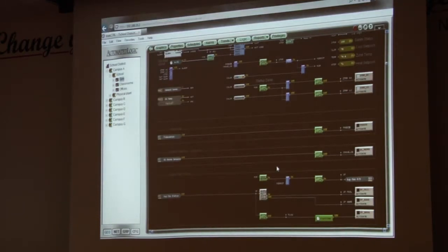The next thing you're looking for is a temperature. A temperature is something that varies. It's not binary. So you're looking for a dark gray hot dog on the left-hand side of your screen that has AI on it for analog input, and it's going to show a little red picture of a thermometer. And that's all that'll really be in there in your systems. I mean, if you start dealing with metering and stuff, we have another hot dog. It shows some purple lines. It's a pulse, but we're not going to deal with pulse. Even if we put a pneumatic module into your system, the pneumatic value is still analog, right? It varies. So we still use an analog input for pneumatics, okay?